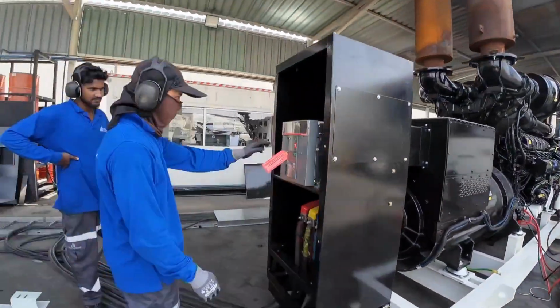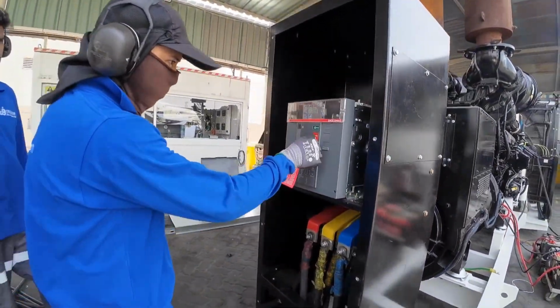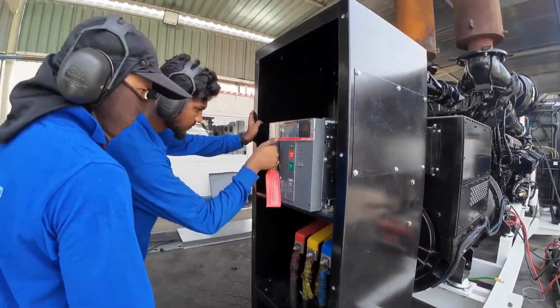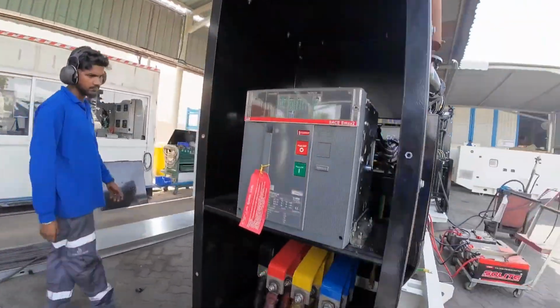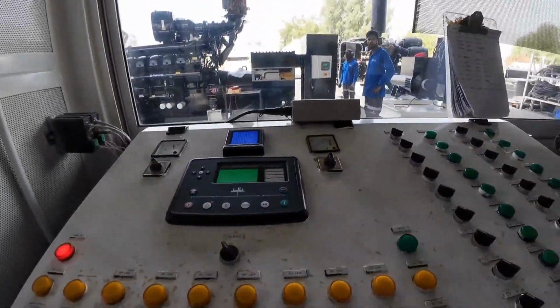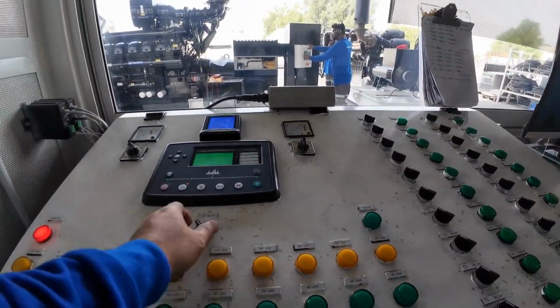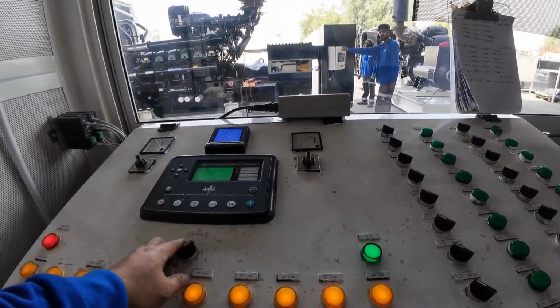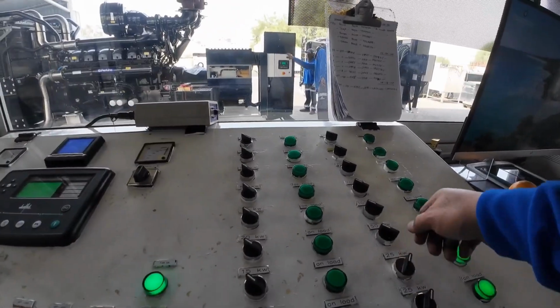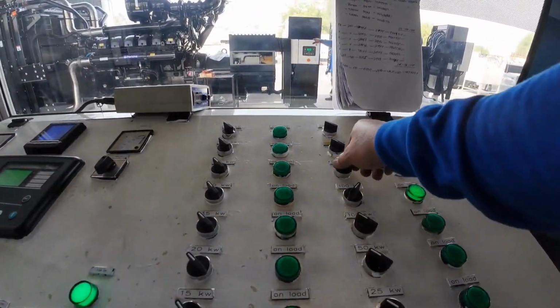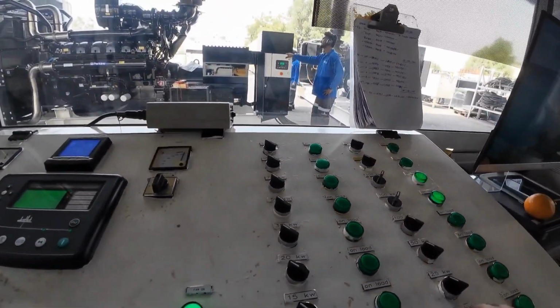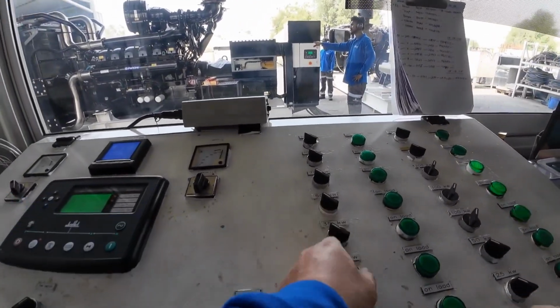I think we are ready for our load testing. Here we're now energizing the breaker and it is on. We're going to put the load at 100 to 110% load, and I'm starting the load bank to have accurate and smooth load application.